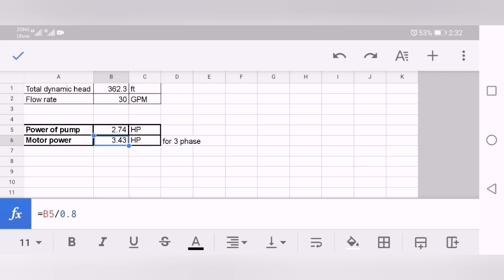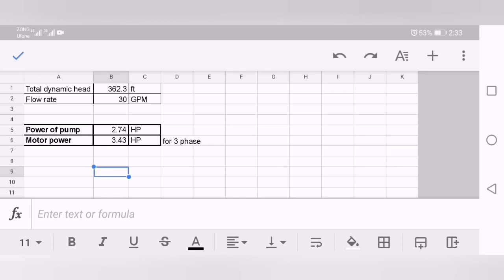My motor efficiency is 0.8, I mean 80 percent. So I just divide this by 0.8 and I get this result: 3.43 HP. You can also add 15 percent factor of safety, so it will be around 4 HP of pump. You will need a 4 HP pump to pump the chilled water or any other fluid.